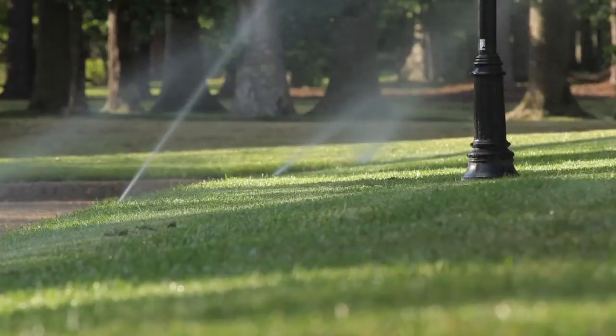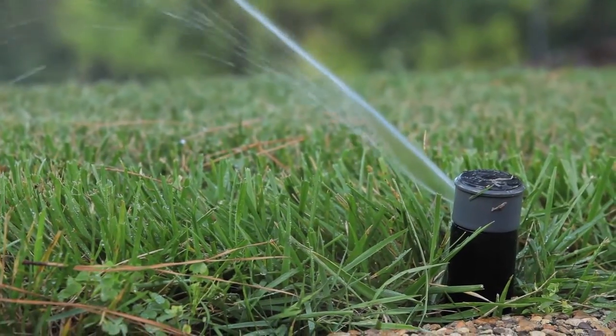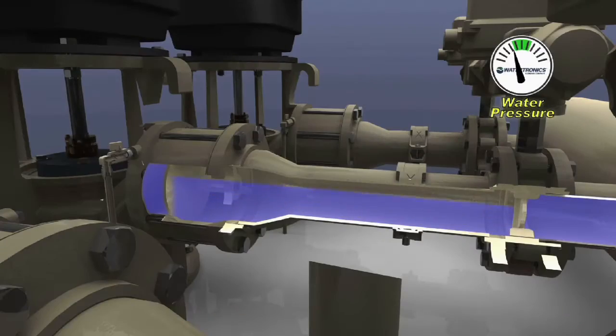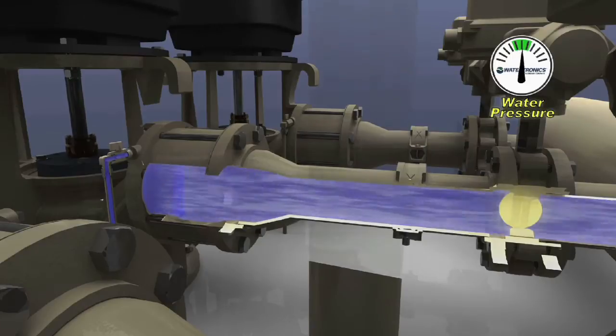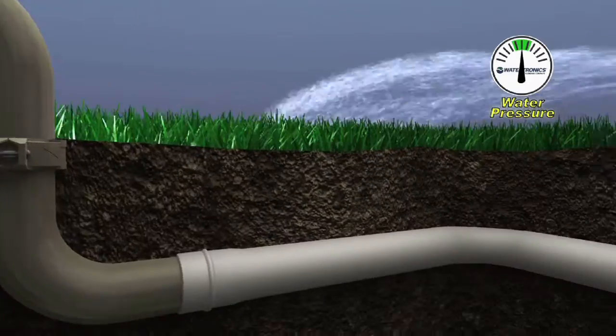We're dealing with an aging infrastructure that varied greatly on the low and high flow ends, and we needed to understand how the project was going to be irrigated. That understanding allowed us to address these issues with the right features, including a higher level of pressure regulation — specifically flow-based pressure regulation, which allows us to assign a pressure set point to a certain flow region. This is important given the aging infrastructure at Governor's Land. We're able to use our patented electronic butterfly valve, which ensures the pump station always starts against a closed valve, greatly reducing any chances of water hammer and extending the life of this very large irrigation system.